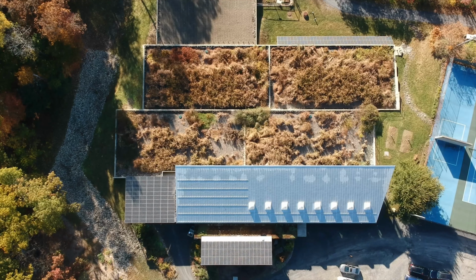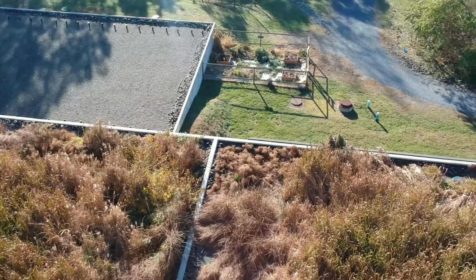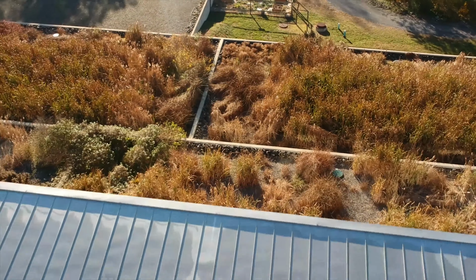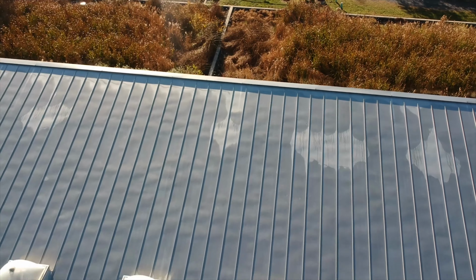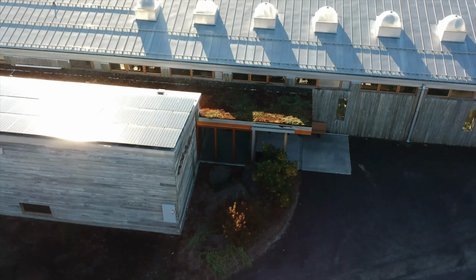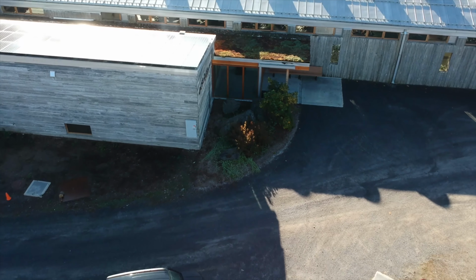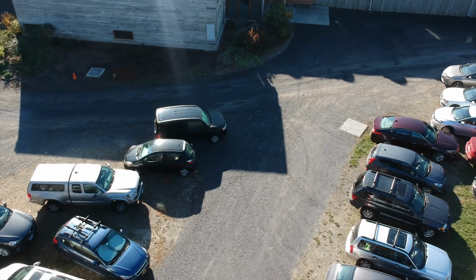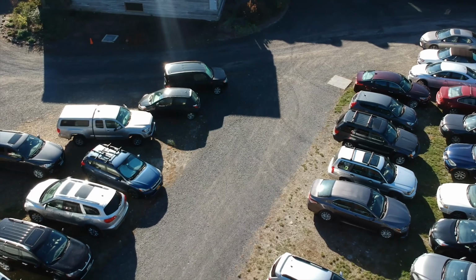So again, the water comes through when you flush the toilet, it goes through the solid settlement tanks, the equalization tanks, through the anoxic tanks, then through the constructed wetland cells, through the aerated lagoon, then to the final polishing in the sand filter, and then it's let out to recharge the aquifer. So that's the process of the eco machine. Any questions before we talk about the Living Building Challenge?